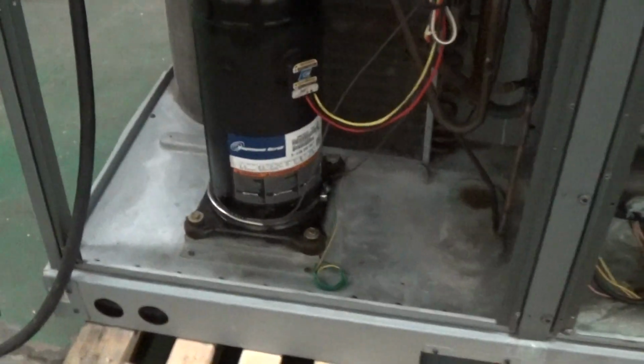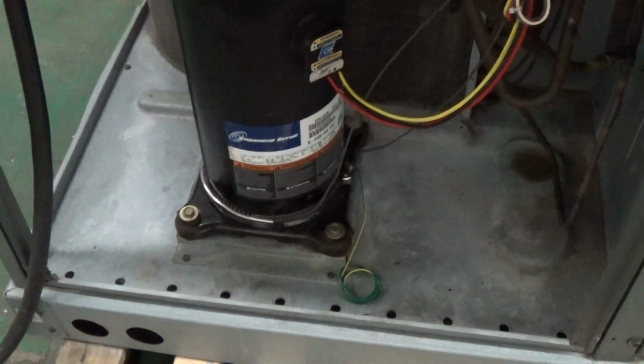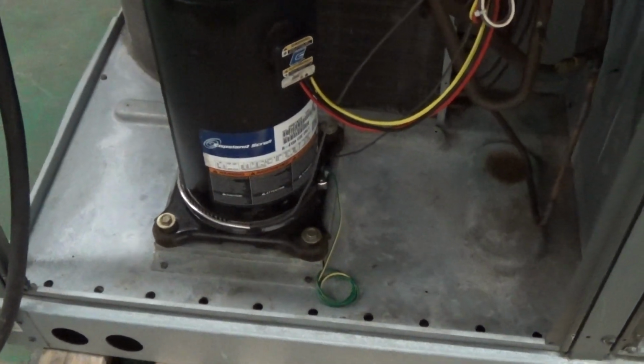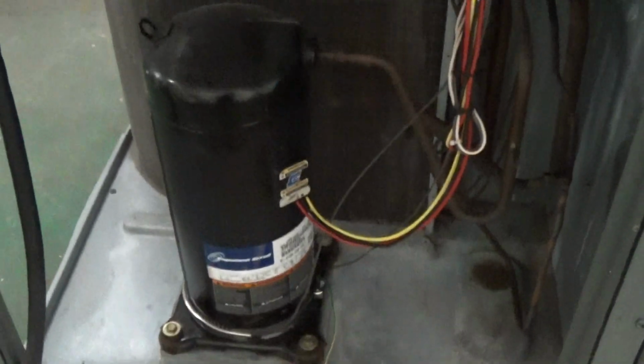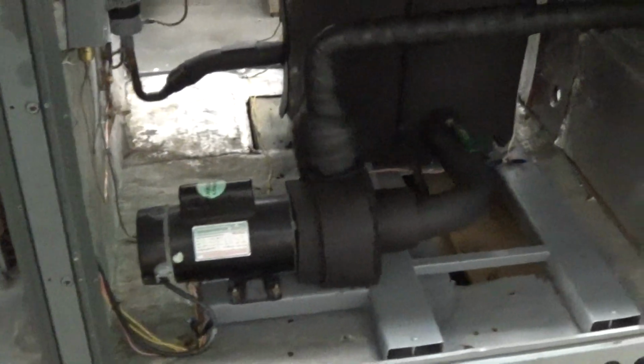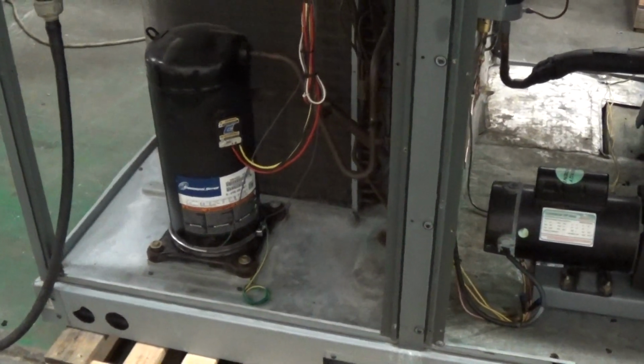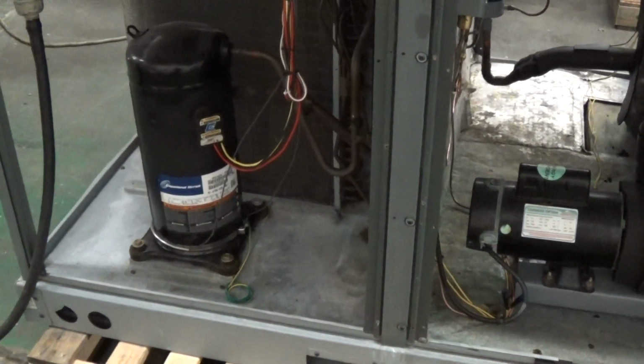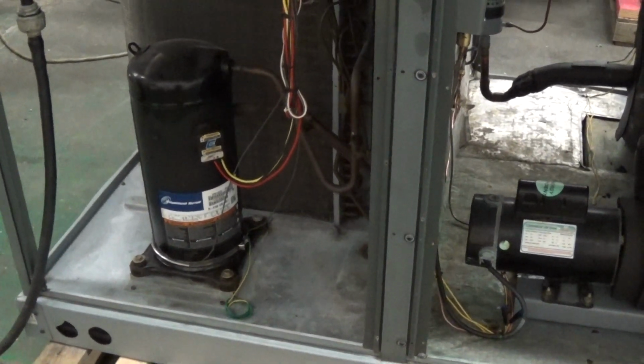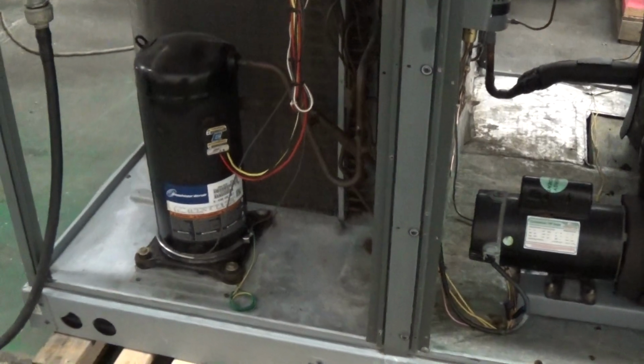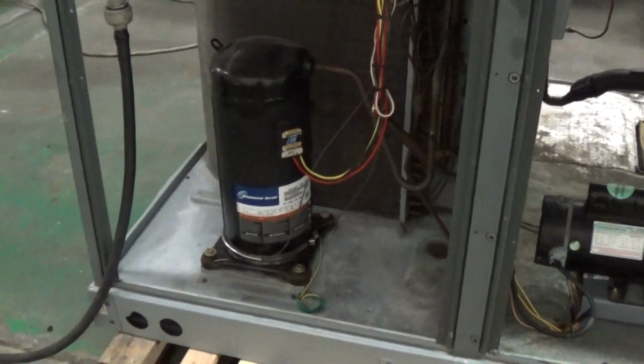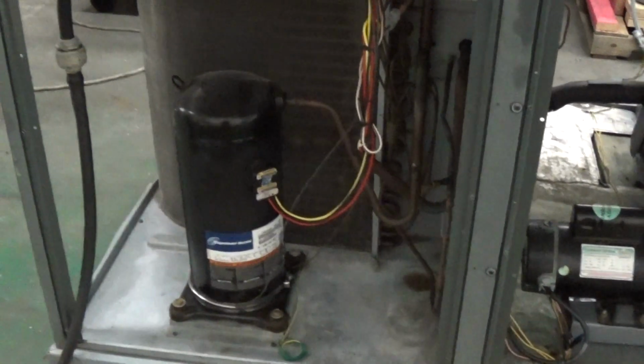The unit, we also added a crankcase heater onto the Copeland Scroll compressor. This is going into an environment that's not particularly cold, but it's nice to have that crankcase heater on there for when the chiller's outside in the colder months. It keeps that refrigerant from gelling up, especially when you're not running.